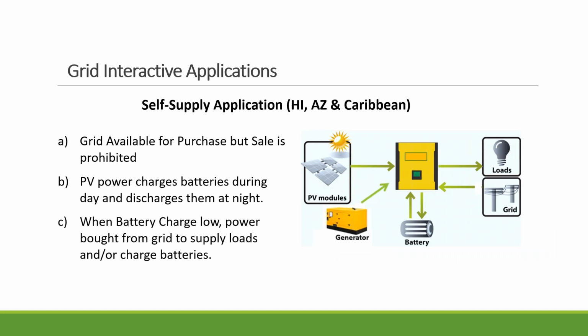When you are living in Hawaii, Arizona, or in many Caribbean countries, either you can't feed the PV production back to the grid, or it does not make any sense to feed excessive power back to the grid because the utility will not give you anything. In those cases, you can design your system so that your PV and storage supply your home load, and you use the grid as a backup. So, for instance, during the day, the PV powers the home circuit and charges the battery, and in the evening, the battery will be discharged to power your home circuit. And if, late in the evening, the battery goes low, the grid can take over to power your home load. And the next day, the same cycle happens again.